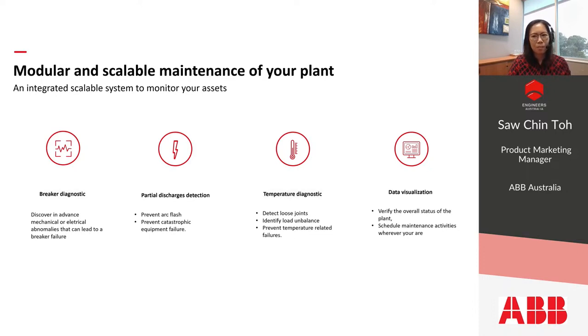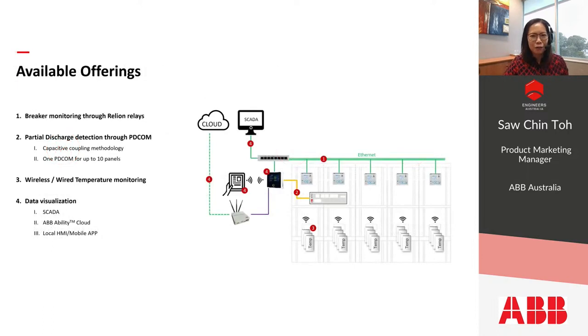The second module is the partial discharge detection, which will prevent arc flash and sudden equipment breakdown. The third module is the temperature monitoring. This will help to detect hot joints and unbalanced load, to prevent all the temperature-related failures in this case. The data visualization is the last module, which then helps to display the health conditions of the switchgear in front of the switchboard or remotely at the plant level control room. This slide will show you the high-level architecture of the SWICOM switchgear monitoring system.